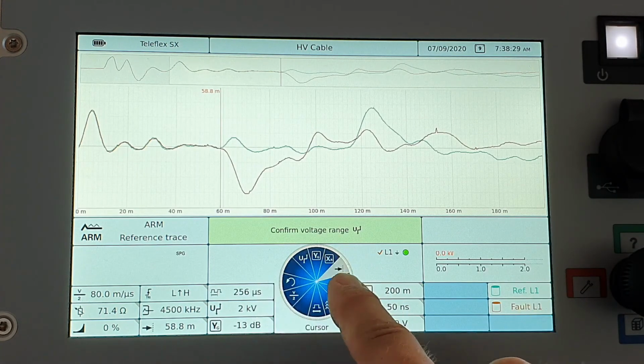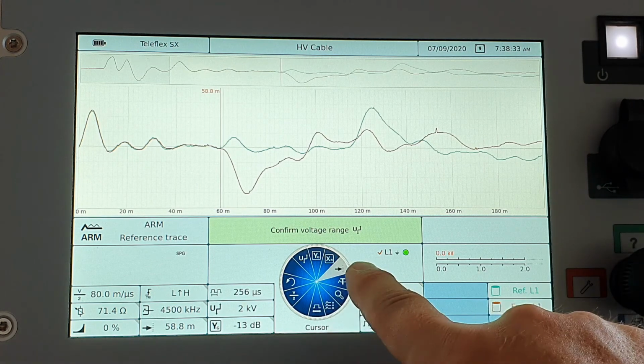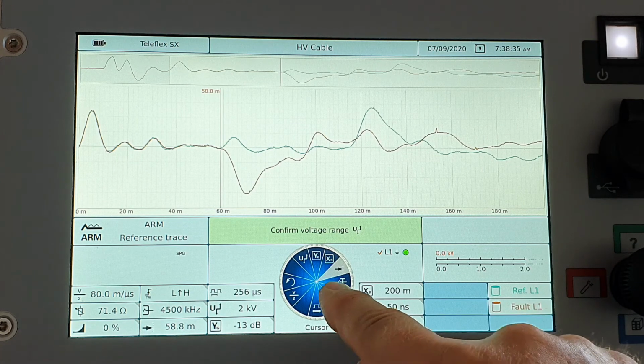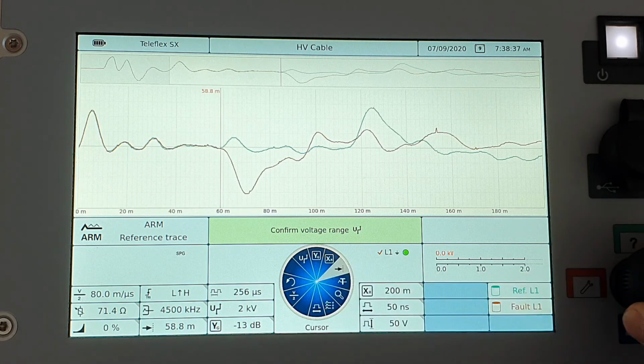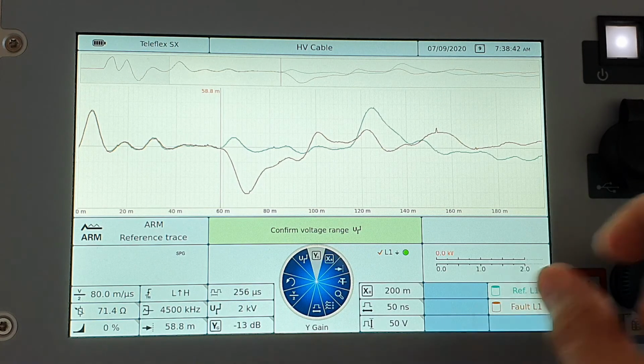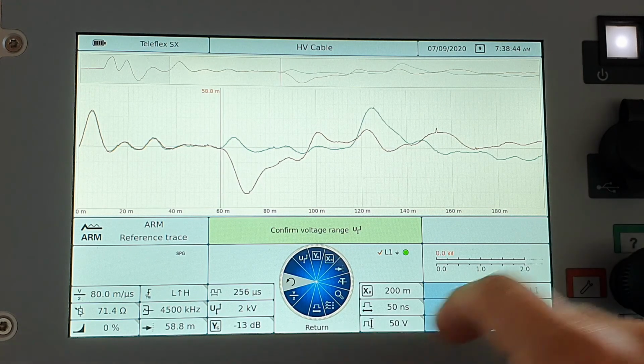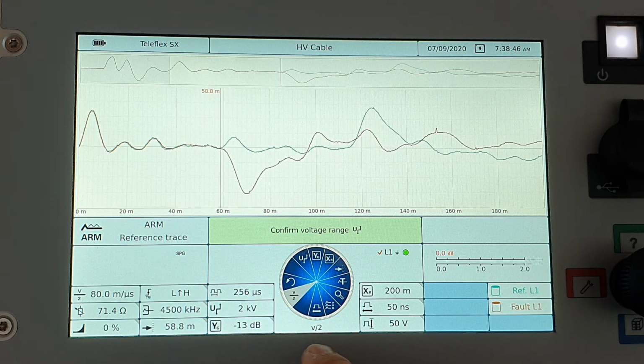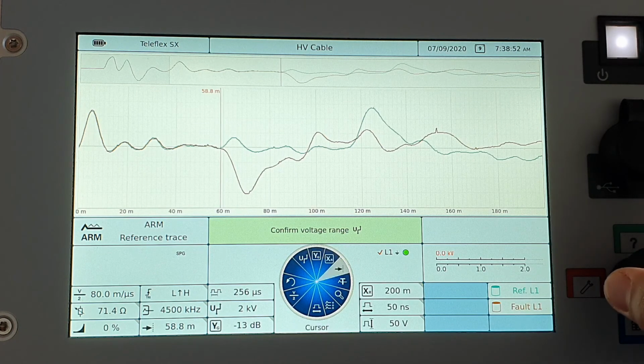The function buttons are always at the same position. So my cursor is always at the 2 o'clock position. My range, X range, is always at the 1 o'clock position. Gain is always at 12 o'clock. Return always at 9 o'clock. Propagation velocity always at 8 o'clock. So if I look for a certain function, I know where to look for it.